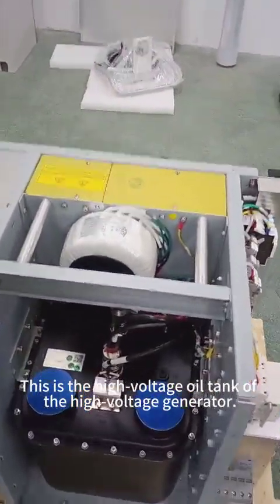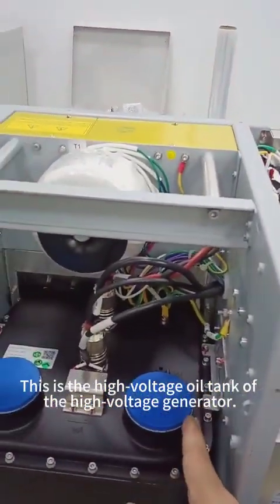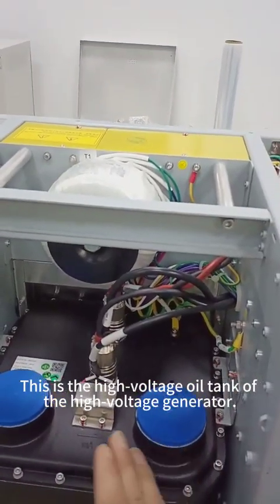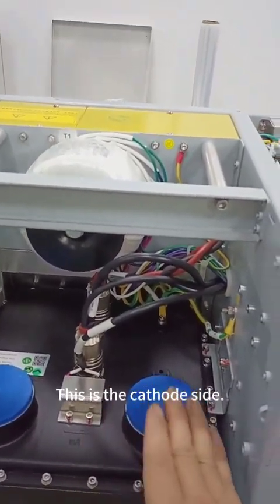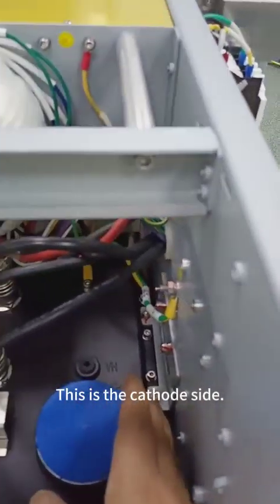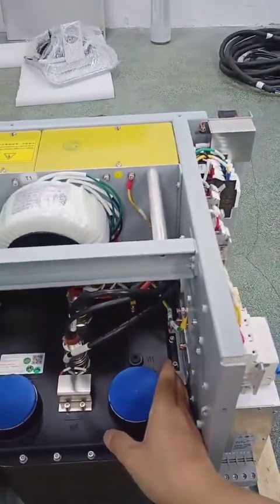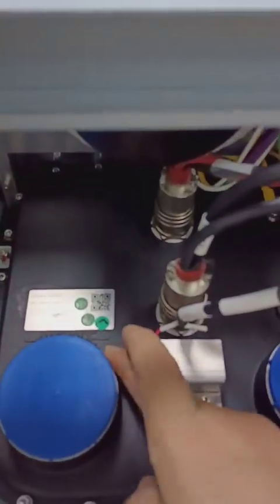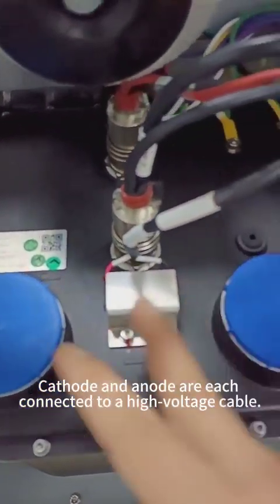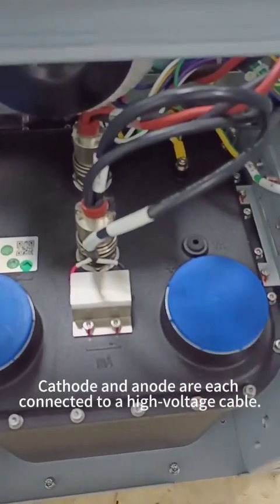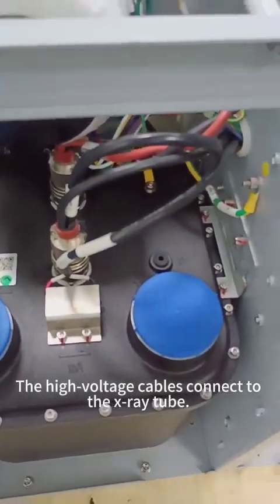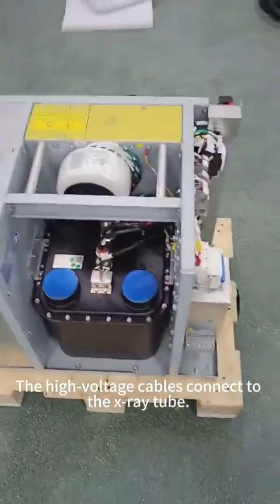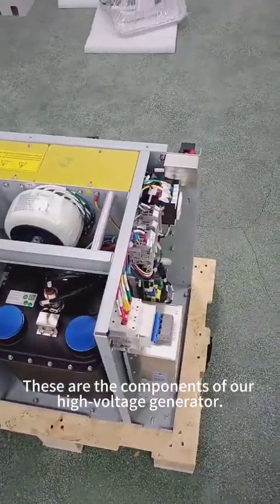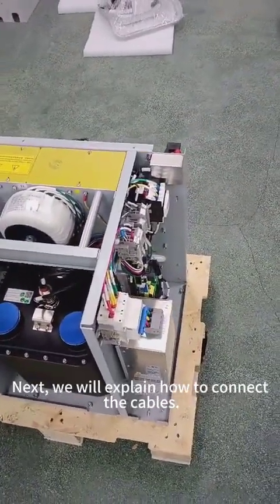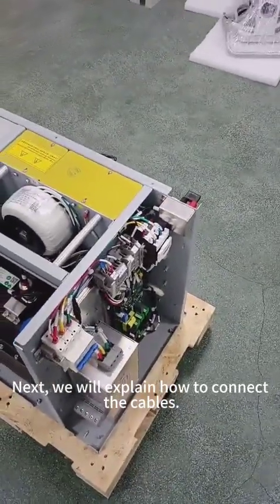Okay, so this is the high voltage oil tank of the high voltage generator. This is the cathode side. The other is the anode side. Cathode and anode are each connected to a high voltage cable. The high voltage cables connect to the X-ray tube. These are the components of a high voltage generator. Next, we will explain how to connect the cables.